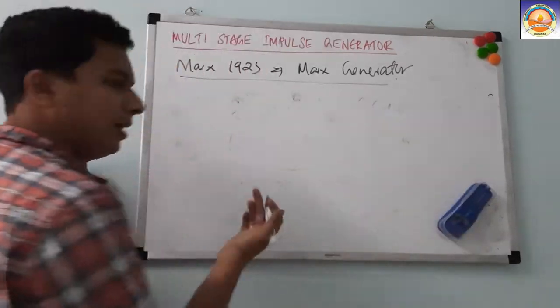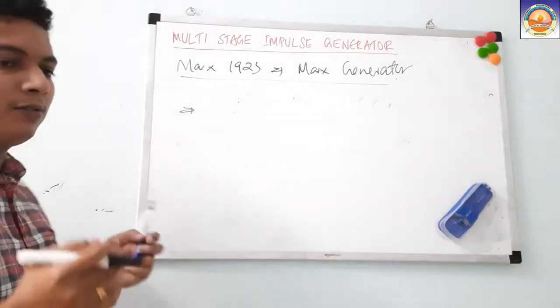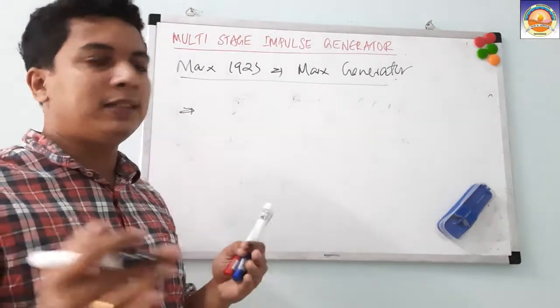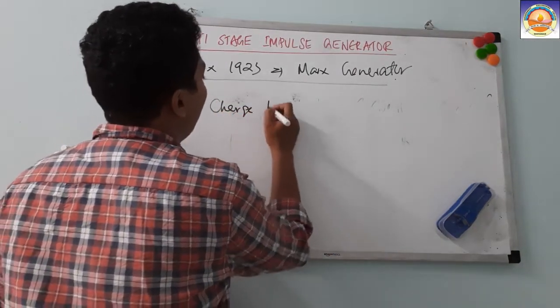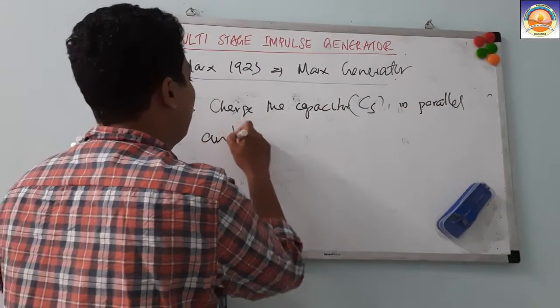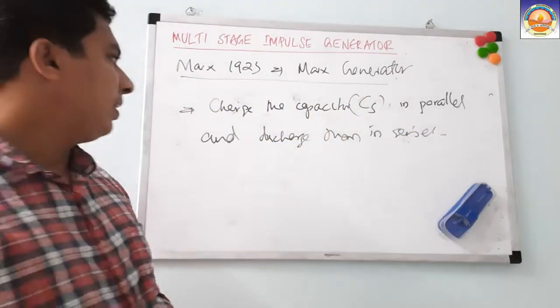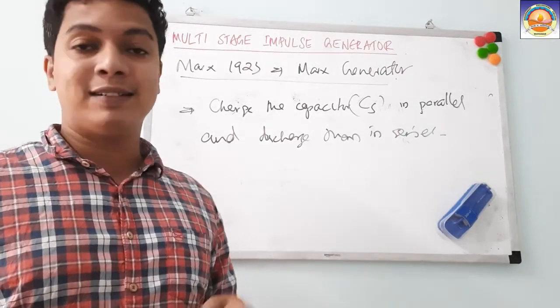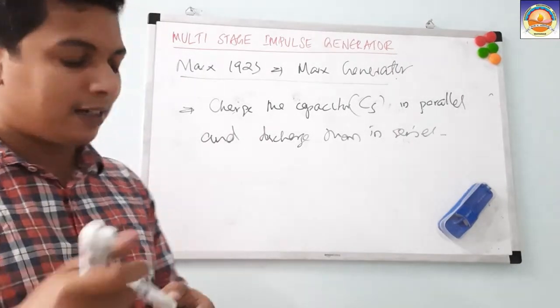Marx's idea is very simple: the whole problem is that we cannot use one big capacitor. So instead, we charge multiple capacitors Cs in parallel, and then discharge them in series through the spark gaps. This was the concept of Marx — charge the capacitances in parallel so all get charged at the same instant, then discharge them in series.